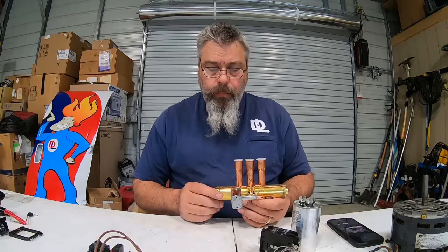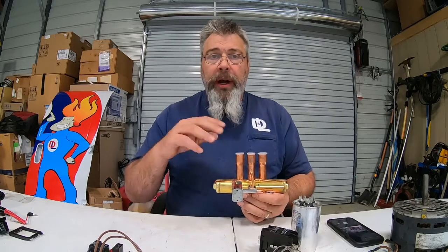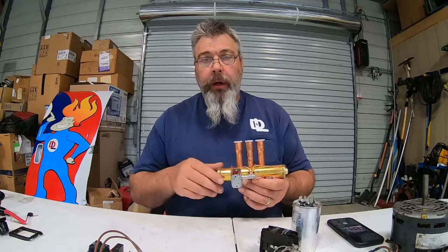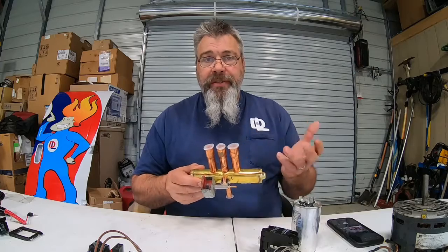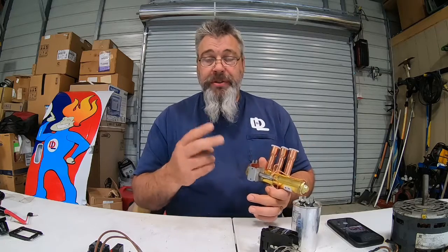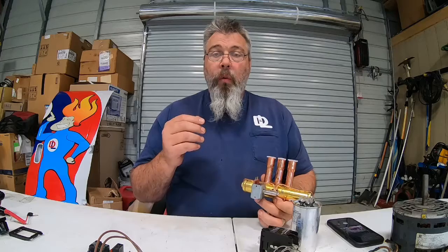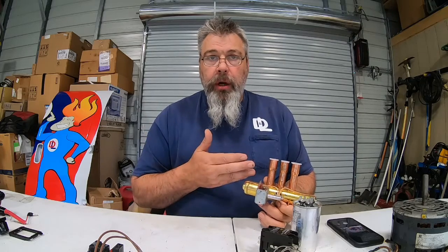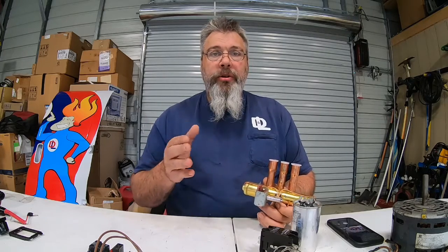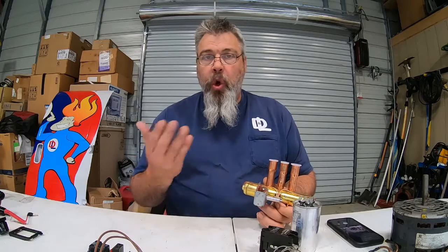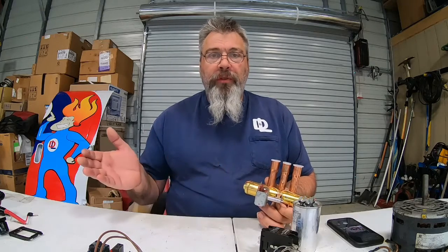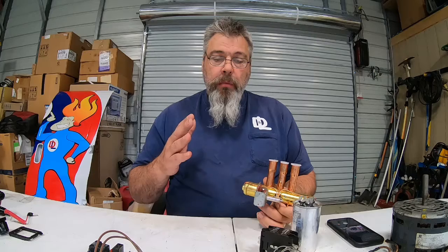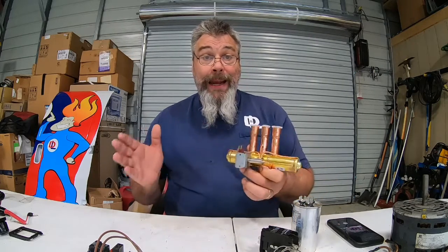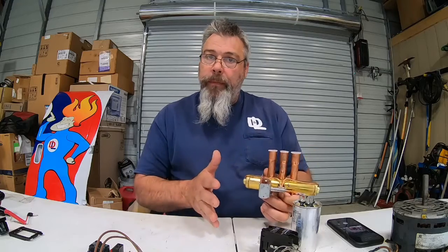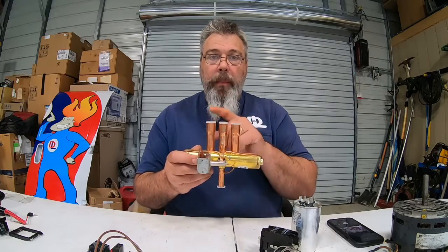Now, in an AC unit, you will not have a reversing valve. There won't be one in there. And why is that? For two reasons. One is we don't run AC in the wintertime, so there's no need to initiate defrost. There's no reason to reverse the flow of refrigerant. But in heat pump mode, in order to get air conditioning and heating out of the same unit, the reversing valve acts as a traffic cop.